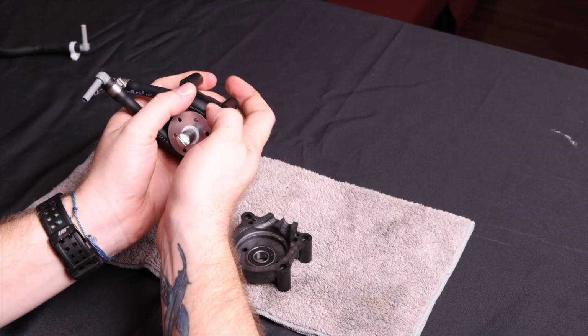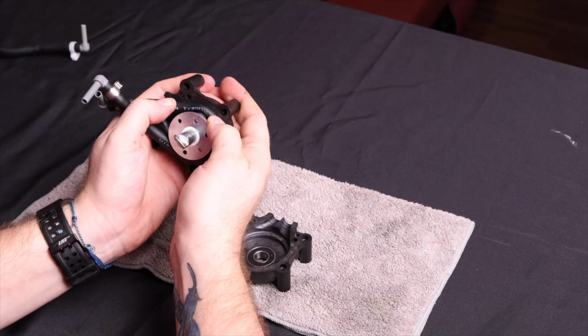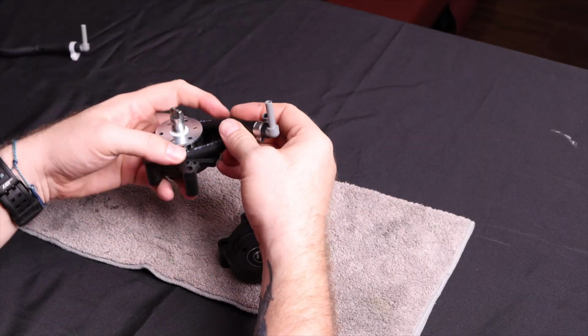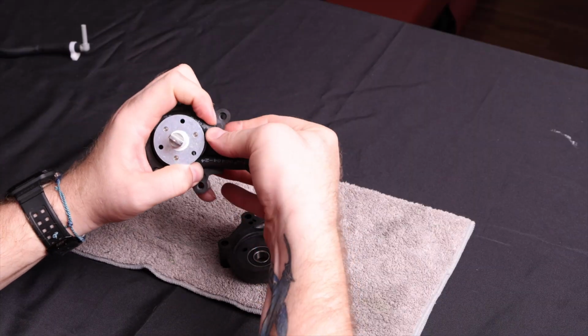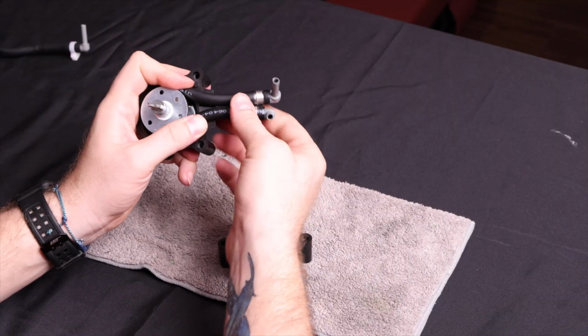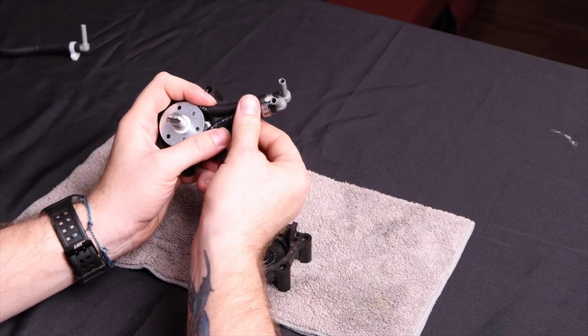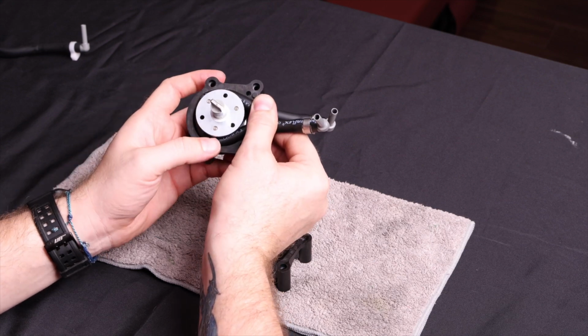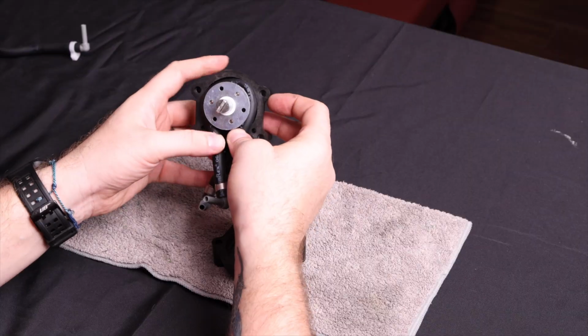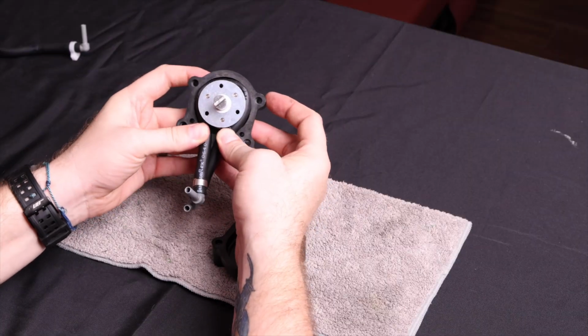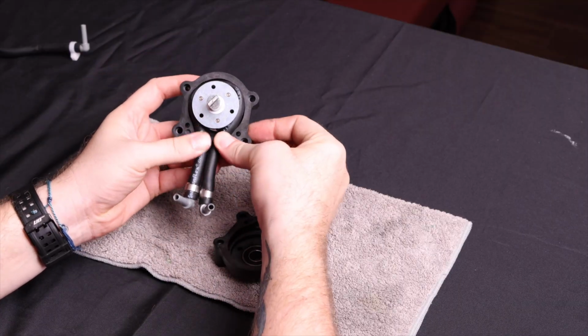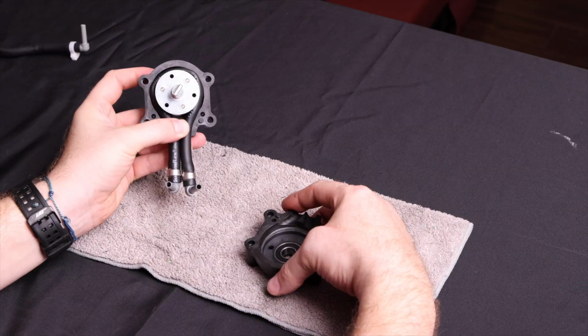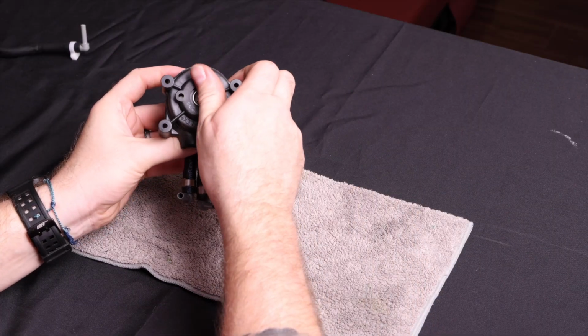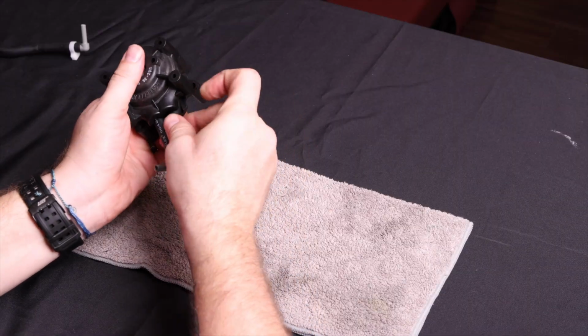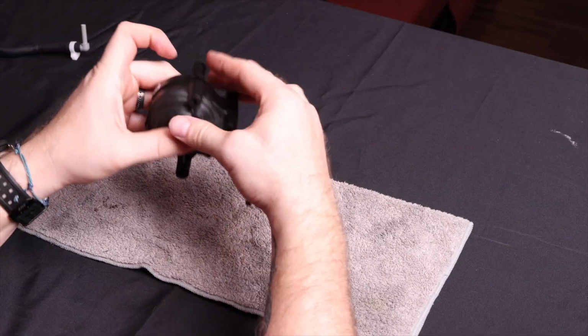Do the same around the rest of the assembly, gently pushing in. Once there, place the tube in the grooves and make sure they are even. If they are not, give them a gentle tug. Once complete, take the lower bell, slide it over the shaft, making sure our tube stays in the groove. And gently squeeze shut.